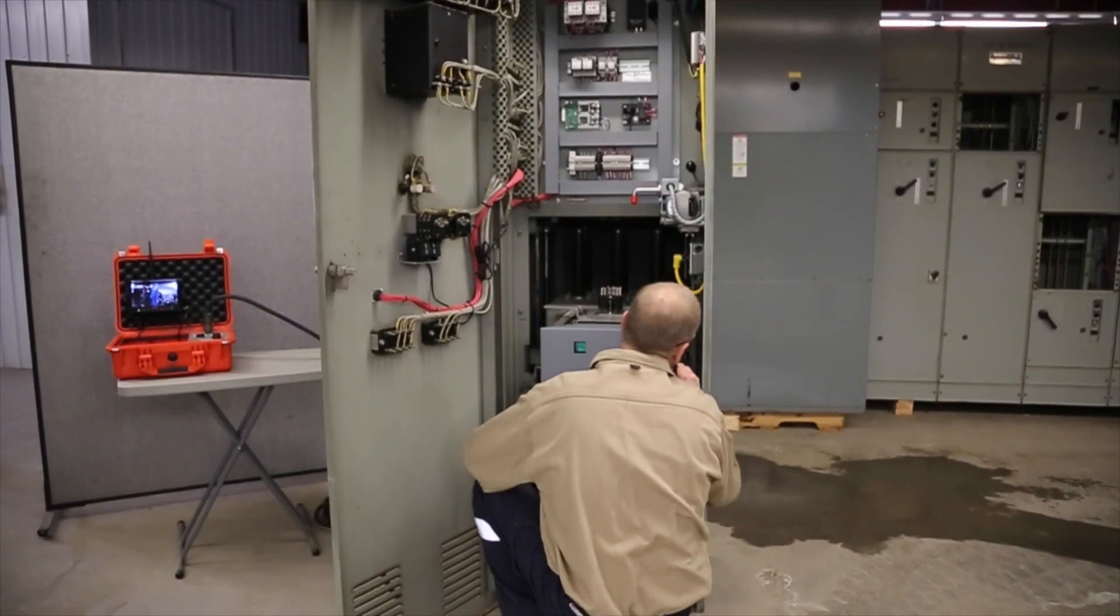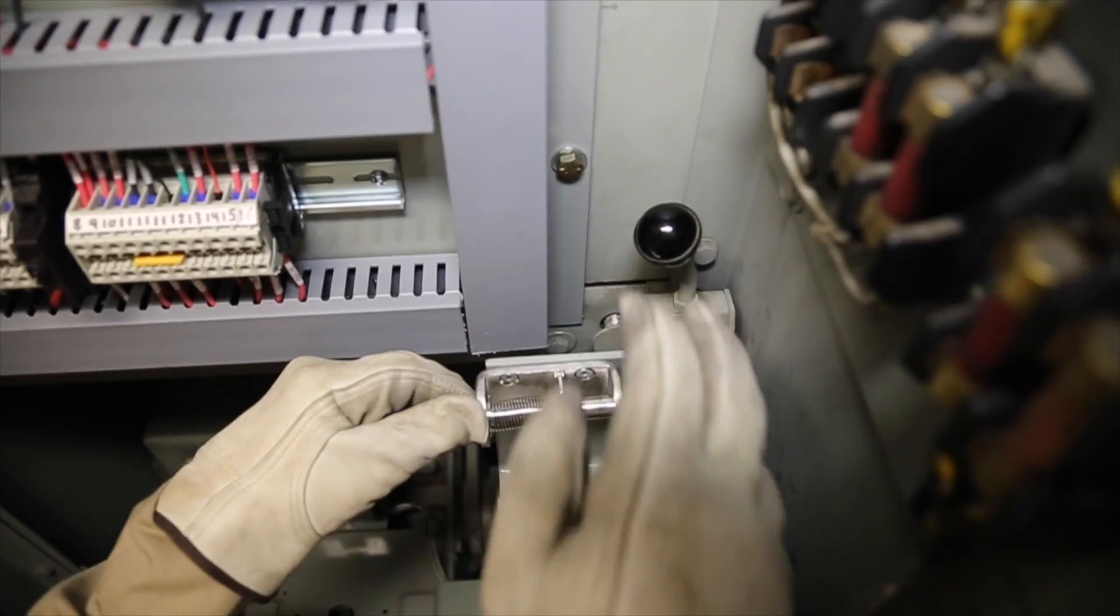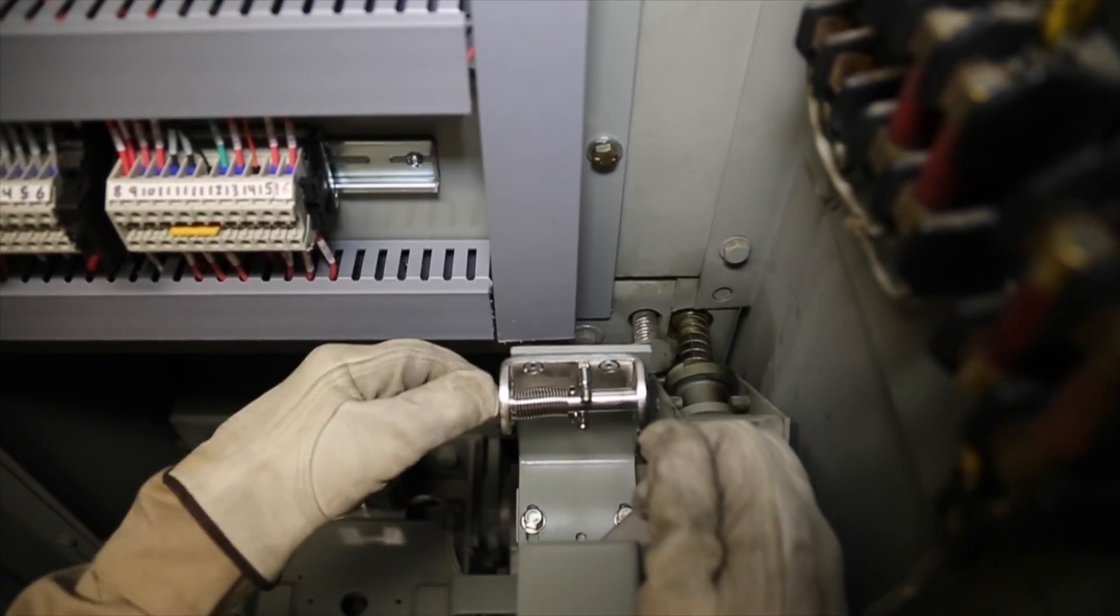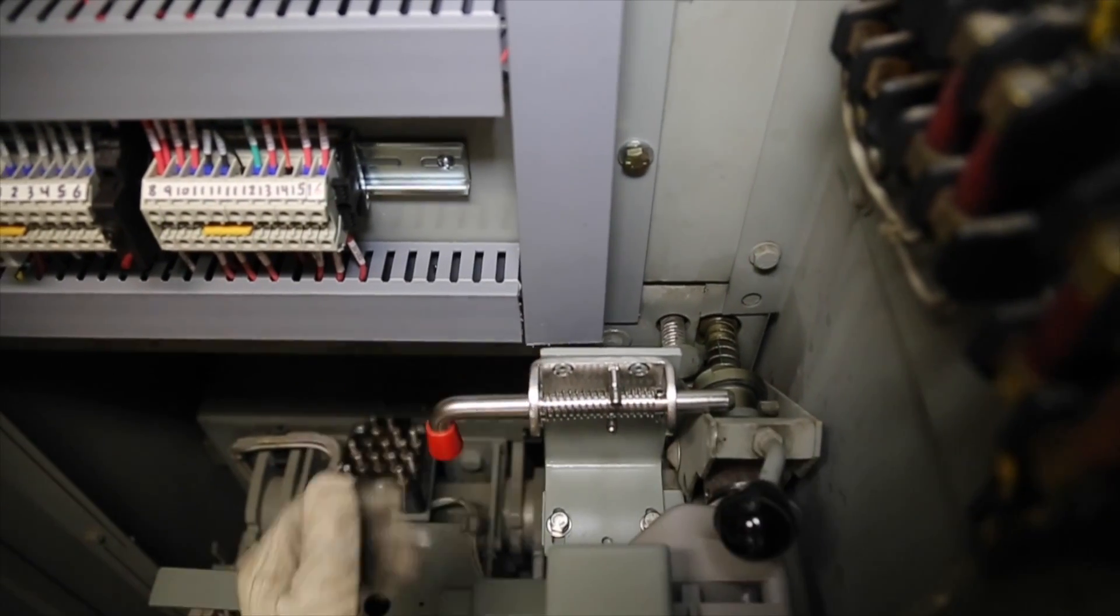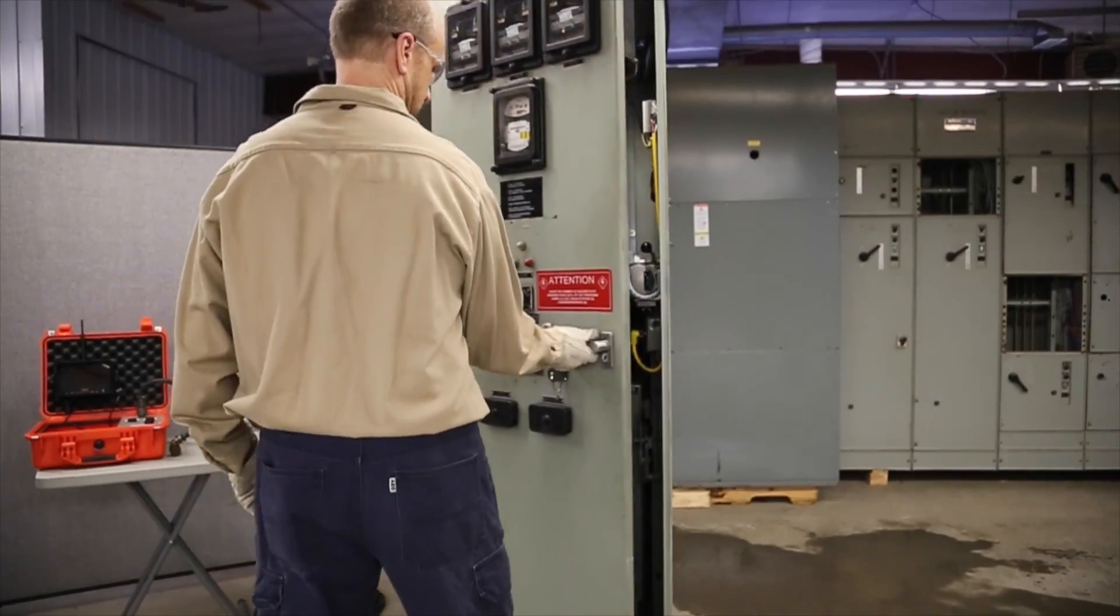Ensure that the breaker positive interlocked roller is centered in the lower notch of the interlocked cam plate. Align the racking motor coupling and engage the clutch handle and hold down pin.